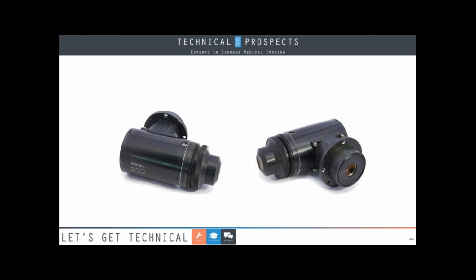Now, if you don't see the bluish light, and that's kind of an example of what you'll see, it'll be a bluish green light, then you're going to want to take that camera off and use a mirror to check the light. If you don't see the light, the image intensifier is the issue. If you see a light after taking the camera off, then your camera's the issue. Piece of cake. There's also a gray filter that goes with the camera that goes in and out. I've had those stick, so sometimes you can just take that camera off or look and see the gray filter sticking, and you'll see if you've solved your problem.